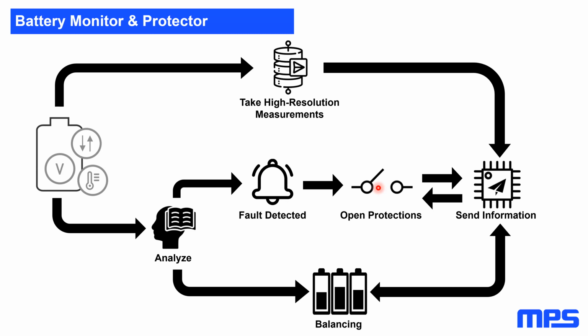The second task is to ensure that the cells operate within a controlled range, generally using passive balancing. Passive balancing is accomplished by enabling a discharge path across any cell with a charge significantly higher than the lowest state of charge. A resistor is used in this discharge path to set a controlled amount of current.